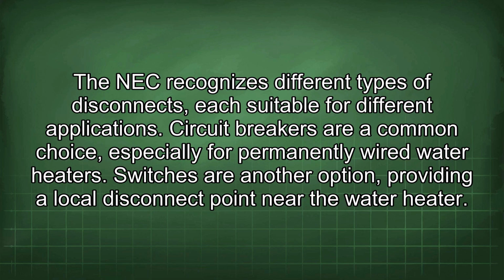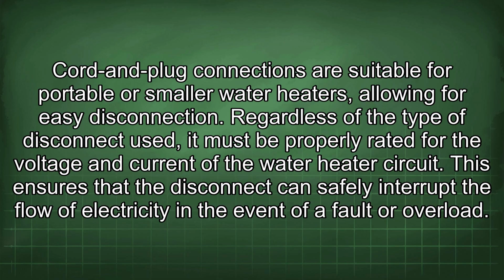The NEC recognizes different types of disconnects, each suitable for different applications. Circuit breakers are a common choice, especially for permanently wired water heaters. Switches are another option, providing a local disconnect point near the water heater. Cord and plug connections are suitable for portable or smaller water heaters, allowing for easy disconnection. Regardless of the type of disconnect used, it must be properly rated for the voltage and current of the water heater circuit. This ensures that the disconnect can safely interrupt the flow of electricity in the event of a fault or overload.